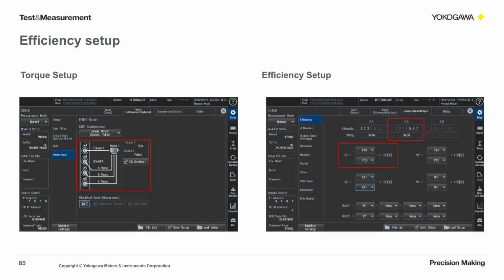For efficiency measurements, we need to configure the motor input from the torque sensor. In the efficiency measure setup, we need to define the equation we want to use. This is power out divided by power in. The input power to the motor is the output of the AC drive. In our setup, we used elements 5, 6, and 7, which were represented by sigma B.